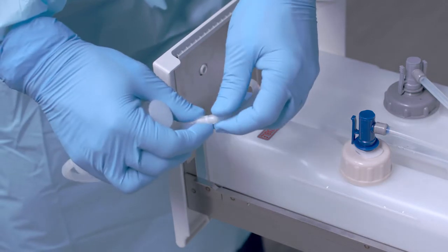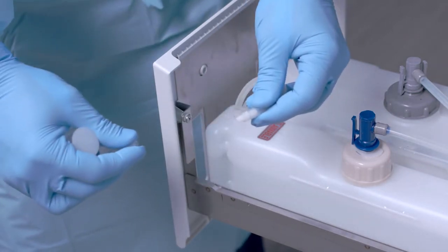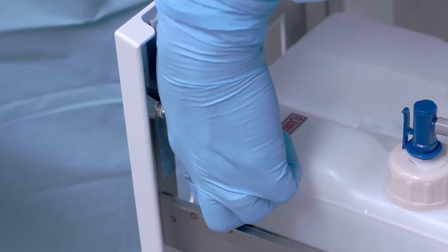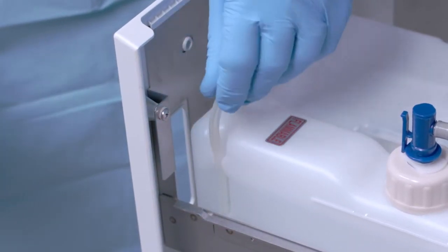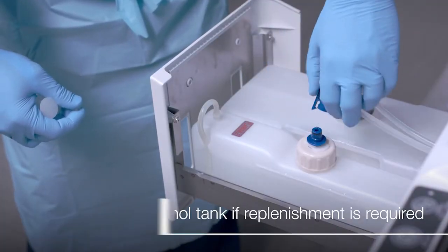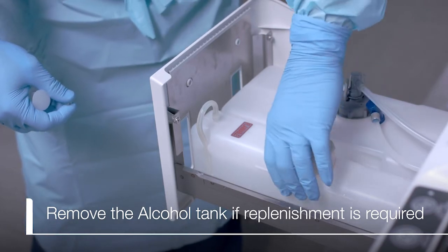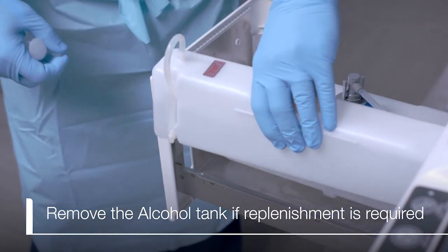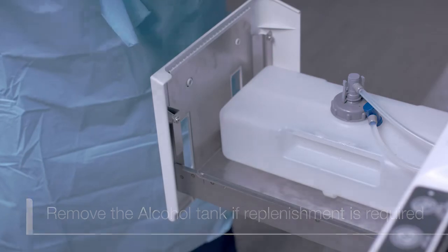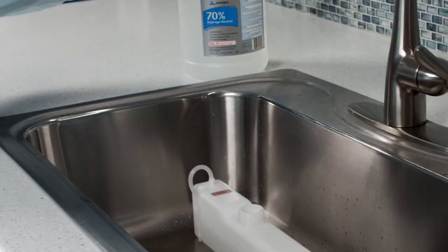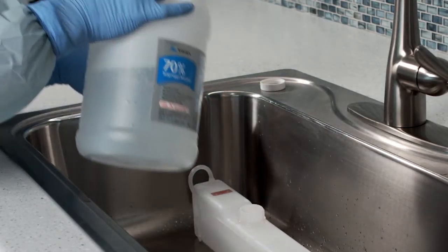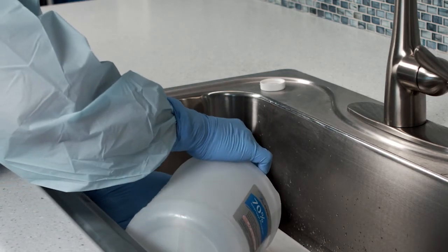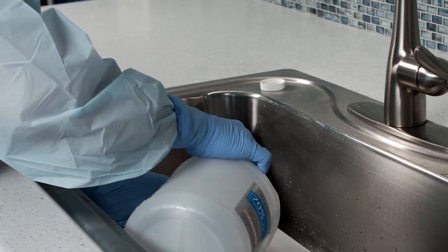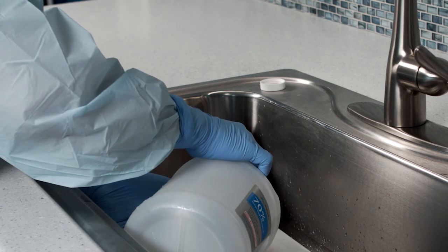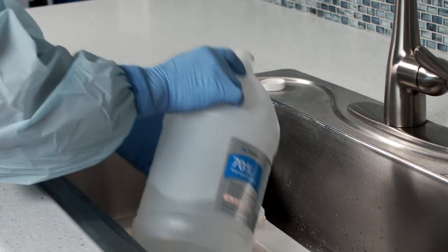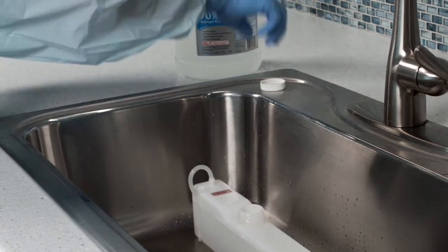Disconnect the tube from the cap on the alcohol tank. Insert the ventilation tube into the container guide. Then, remove the tank from the detergent/alcohol drawer. Now, carefully pour the medical-grade 70% ethyl alcohol or isopropyl alcohol into the alcohol tank if replenishment is necessary. If any is spilled, simply wipe it with a clean cloth and tighten the cap.